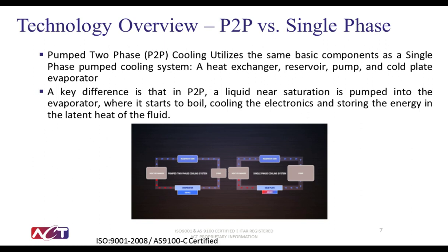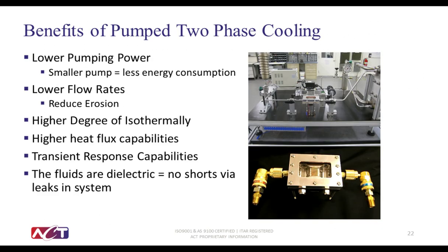As can be seen in the schematic below, pump two-phase cooling utilizes the same basic components as the single-phase pump cooling system we just discussed: a heat exchanger, reservoir, pump, and a cold plate evaporator. A key difference is that in P2P, a liquid near saturation is pumped into the evaporator where it starts to boil, cooling the electronics and absorbing and removing the waste heat via latent heat of vaporization.